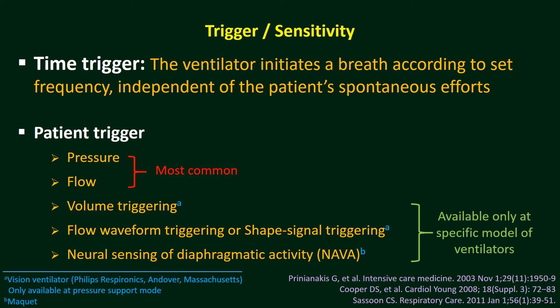So, this is pressure trigger. In the ventilator, you will find this setting as minus, so minus 0.5, minus 1, etc. How does it work? This is the ventilator circuit, this is the inspiratory circuit and expiratory circuit, and here is the patient's end. When the patient does not take any breath, inside this circuit there is zero pressure. But when the patient tries to take a breath, there will be some negativity inside the circuit. If this negativity is more than what we set as trigger, then the ventilator will understand the patient is trying to take a breath and deliver a breath.